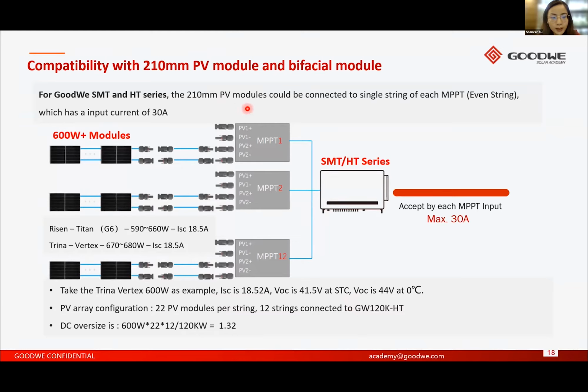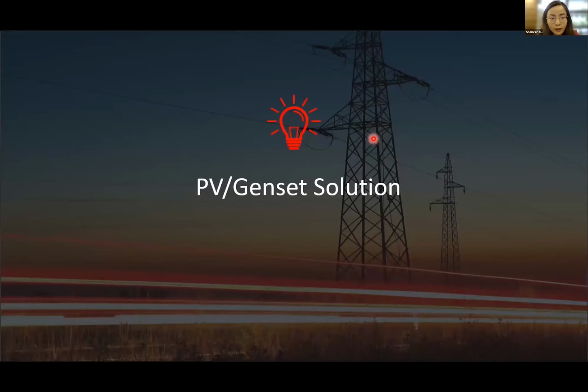Here we need to pay attention that we should connect the PV strings to the even inputs of the MPPTs, because the even strings can actually allow higher input current. In Southeast Asia, there are many independent islands, so the PV and genset solution is a major concern.